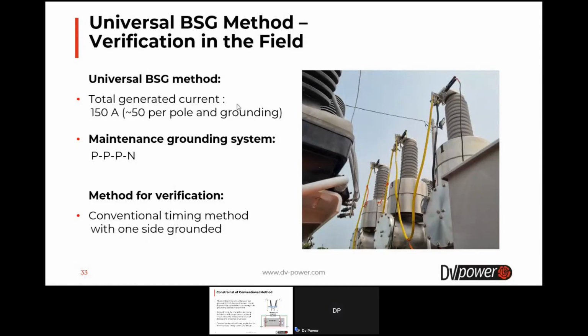Total generated current was about 150 amps. That means about 50 amps per pole and grounding. And of course, the maintenance grounding system was PPPN, where, as you can see, terminals from one side of the circuit breaker are connected to each other by these common cables, and then one of them is connected directly to the grounding terminal. And we used the conventional timing method for the verification when we removed one side grounded. That means the conventional timing method is performed when one side of the circuit breaker is grounded.